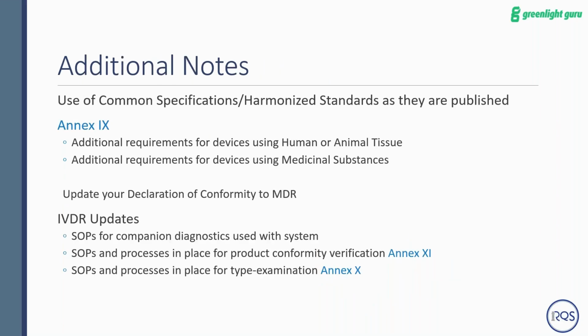Additional notes. Outside of implants, there are additional requirements for devices using human or animal tissue, and make sure you're complying with that, not only in the GSPR section, but also in the main text of the MDR. Same with medicinal substances being used in devices, so potentially catheters that are coated with drugs, or combination devices, making sure that you are complying with the new updates in the MDR for that. A big thing that could get overlooked is you're going to have to update your declaration of conformity. So you have to say that you now conform with the MDR versus MDD. That's all companies, you're going to have to do this. So make sure you're thinking about that. It seems simple, but you don't want the auditor, once they're there, to ask for your declaration of conformity and it show old standards.